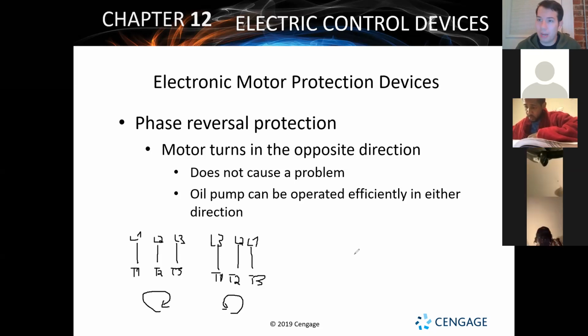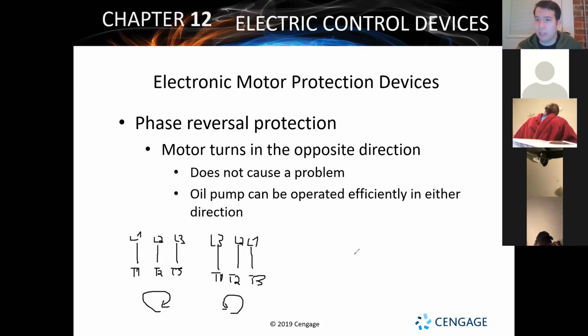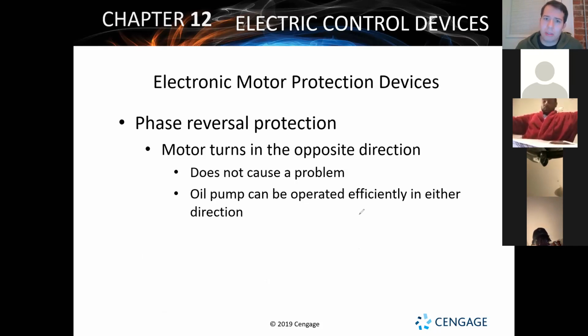Now, will the motors be damaged? No. The motors will generally be in pretty good condition, but the system will shut off, because it's going to try to start up and realize, hold on a second, I can't actually move the air in the right direction. I can't move the refrigerant in the right direction, and my thermostat's not being satisfied, so I just need to shut the system down for the time being. But phase reversal protection stops that from happening, and you don't have to worry about the motors running backwards, basically.